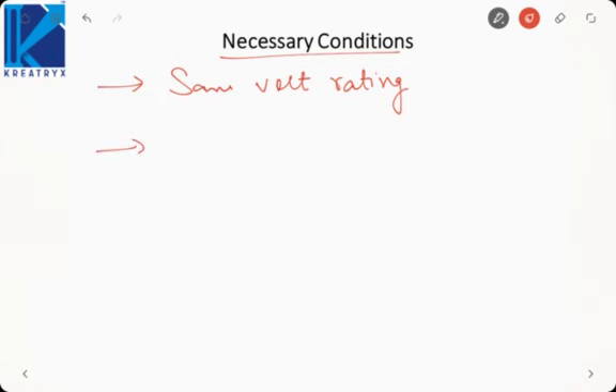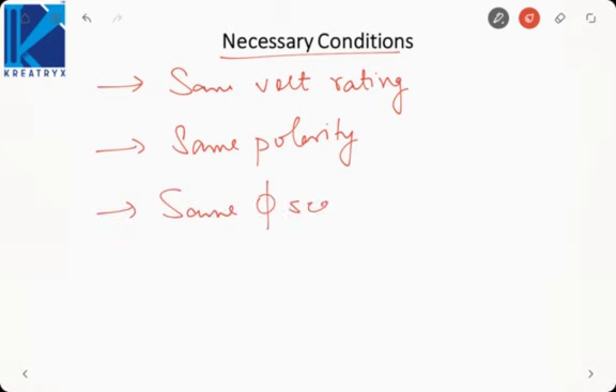Next one was same polarity to avoid any circulating current. Next, same phase sequence and same phase shift. These are four necessary conditions for parallel operation of the transformer.